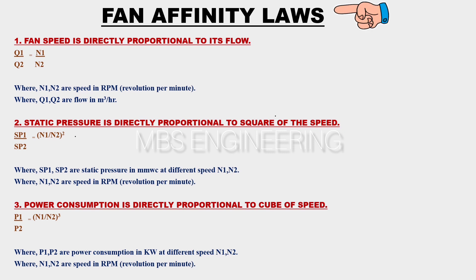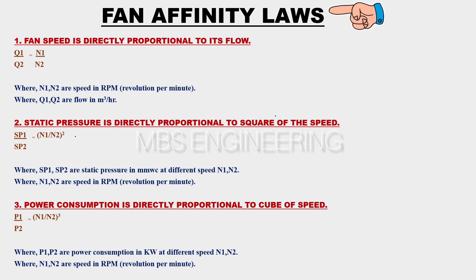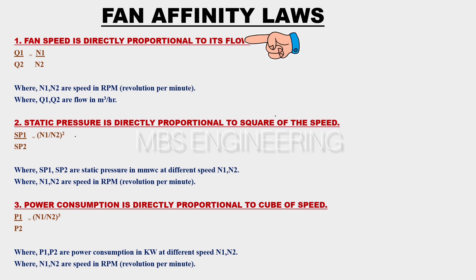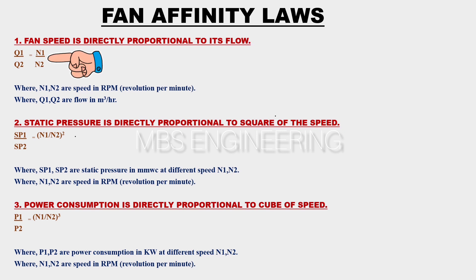Next, we learn about the formula for fan affinity laws. It states the relationship between a fan's flow, static pressure, speed, and power consumption. The first affinity law: fan speed is directly proportional to its flow. The fan speed N1 divided by N2 is directly proportional to its flow Q1 divided by Q2.